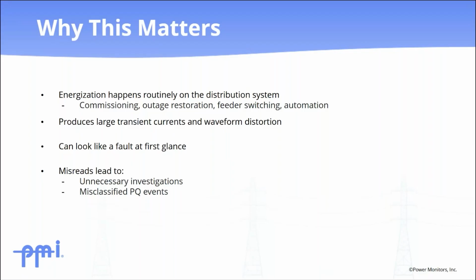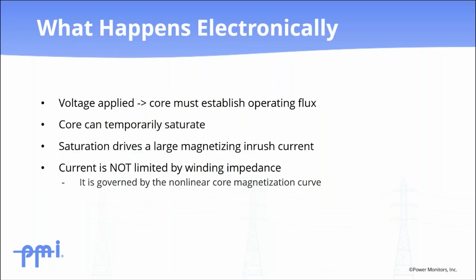The goal of this paper and this session is to make sure that you can look at a recording and confidently say, that's a transformer being energized, instead of chasing down a phantom fault. When voltage is first applied to a transformer winding, the magnetic core has to establish its operating flux level. Depending on exactly where on the voltage waveform that switching happens, the magnetic flux in the core can temporarily push past its normal operating range and drive the core into saturation.